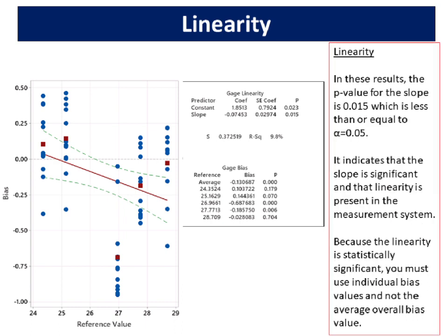In these results, the p-value for the slope is 0.015 which is less than or equal to alpha equals 0.05. It indicates that the slope is significant and that linearity is present in the measurement system. Because the linearity is statistically significant, you must use individual bias values and not the average overall bias value.